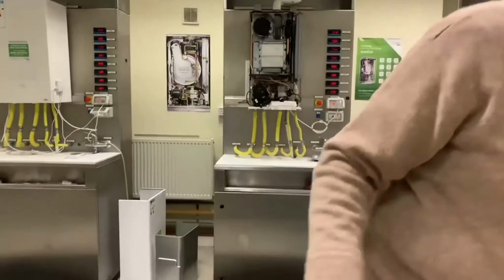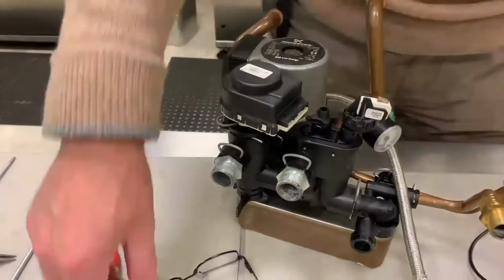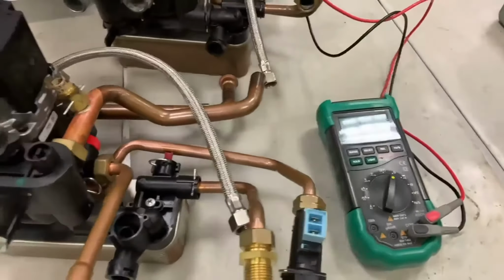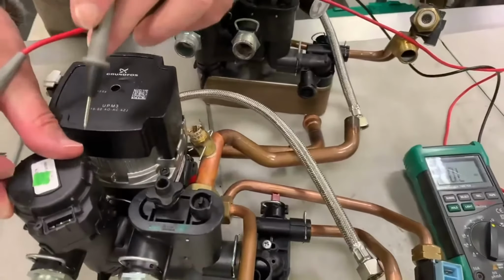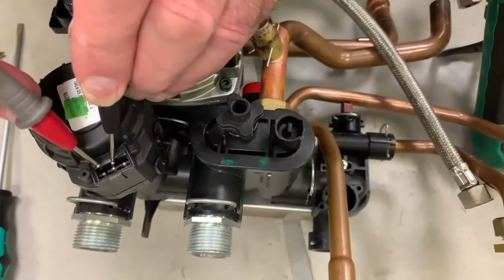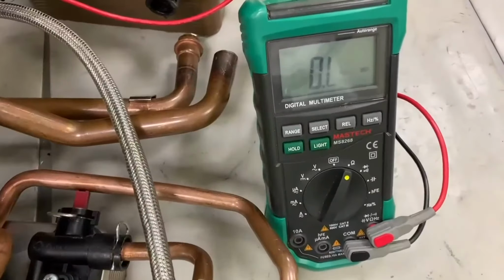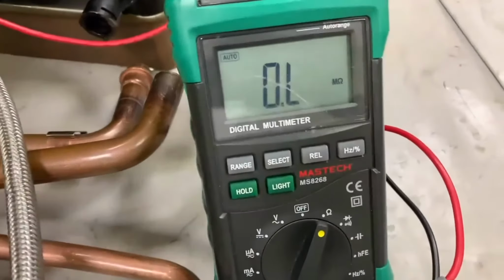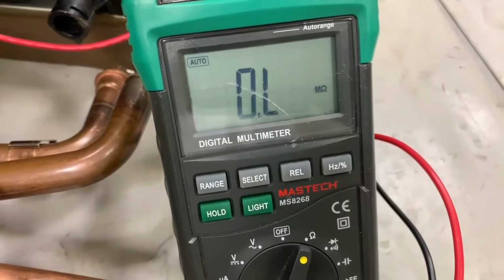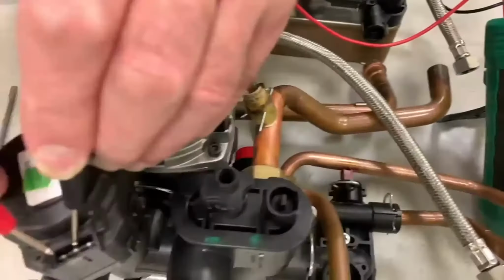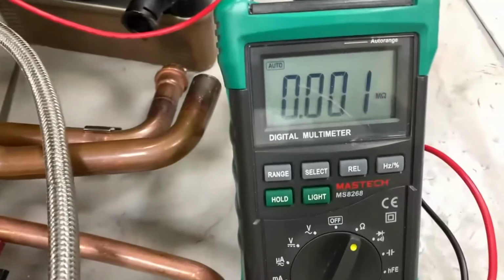We spoke about testing motors with resistance. The actuator is a motor, so you can test it with one probe on the middle for the neutral. Test one side to the other. One on this side. I think this one is 800 ohms, so we're getting OL. So this is in the other position, so I'm going to go from the other side, middle to the other side.